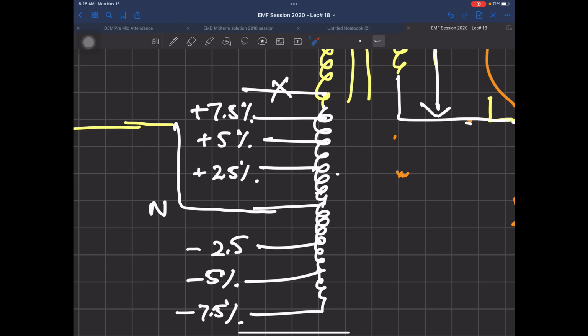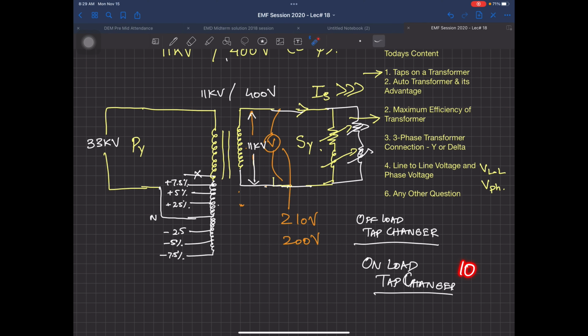So this is a power electronics box, and this is how you do tap changing on load. This type of tap changer is approximately 10 times more expensive than the off-load tap changer because of the huge circuitry involved, but the advantage is enormous since you don't have to take off the load. In Pakistan though, we already have load shedding.